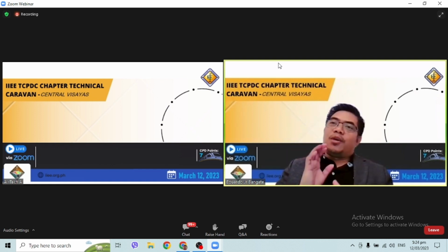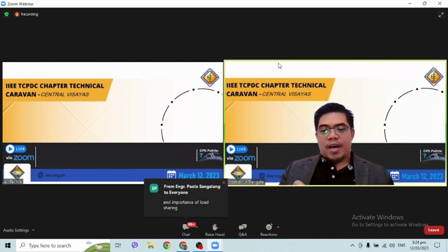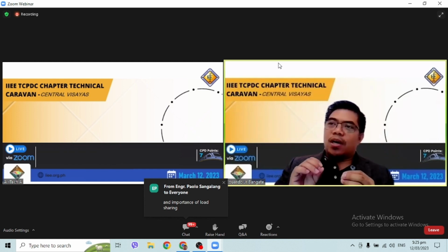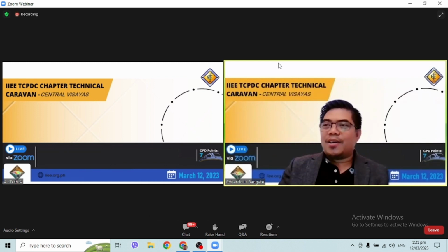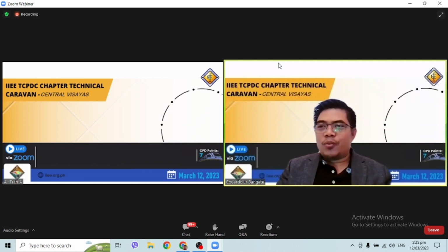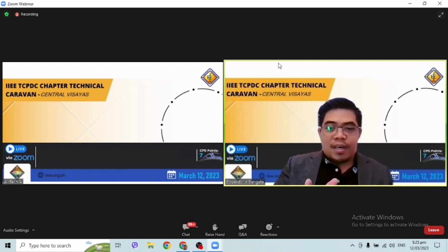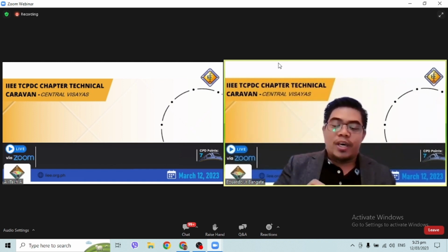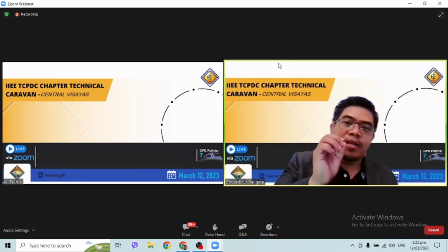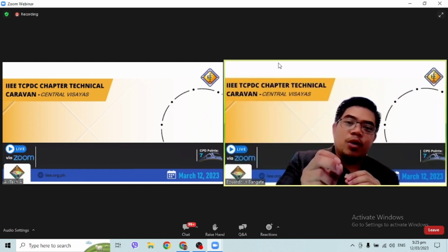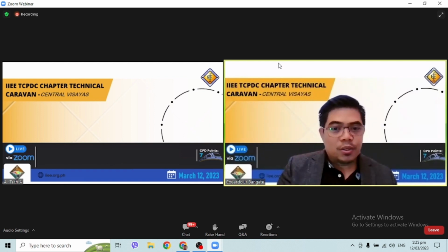When you design a backup generator, you have to understand the type of the load that you have. When you have a load that is constantly running or constantly connected to the generator, it will operate continuously. It will be the prime power. It will be on island mode. So it means that you don't need to parallel, right? Then one generator will be okay because you will satisfy the requirement that the generator will be operating at its optimum level of 70 to 80% of its rated capacity. So that would be good.